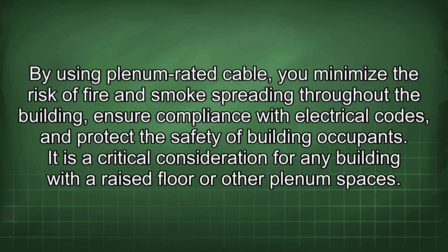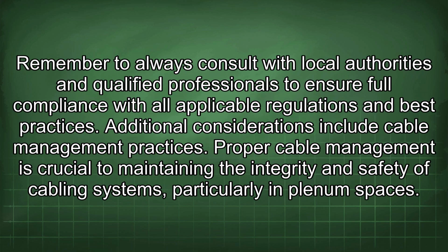By using plenum-rated cable, you minimize the risk of fire and smoke spreading throughout the building, ensure compliance with electrical codes, and protect the safety of building occupants. It is a critical consideration for any building with a raised floor or other plenum spaces. Remember to always consult with local authorities and qualified professionals to ensure full compliance with all applicable regulations and best practices. Additional considerations include cable management practices.